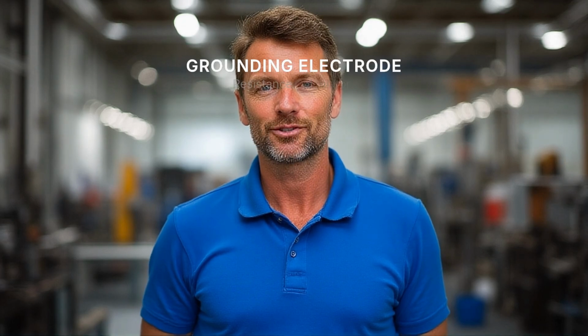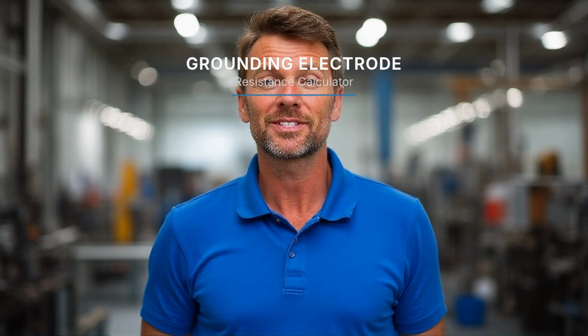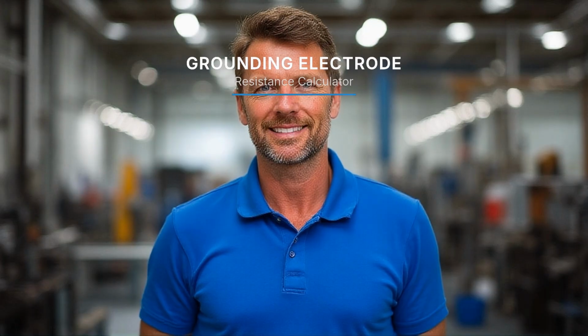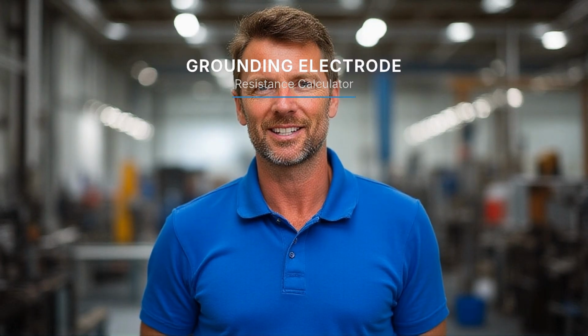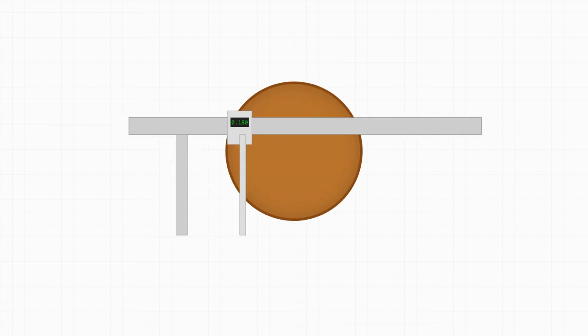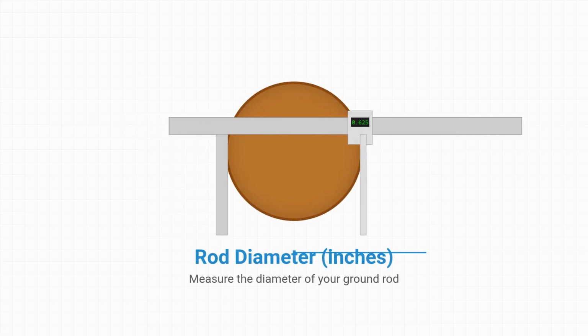This is the grounding electrode resistance calculator, which determines the resistance value of a ground rod installation based on your specific site conditions. Let's walk through the 3 input fields you'll need to complete. First, enter the rod length in feet. This is the total length of your grounding rod. Second, input the rod diameter in inches. Measure the diameter of your ground rod.